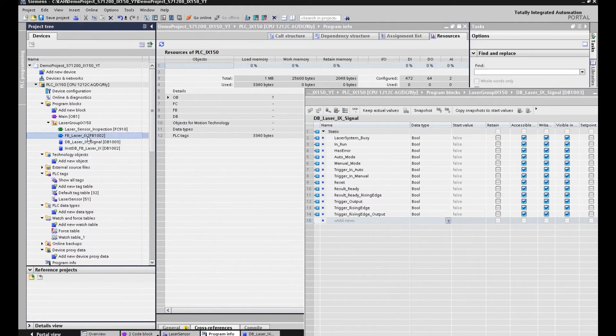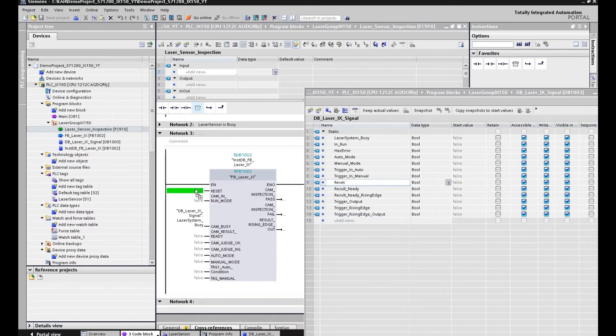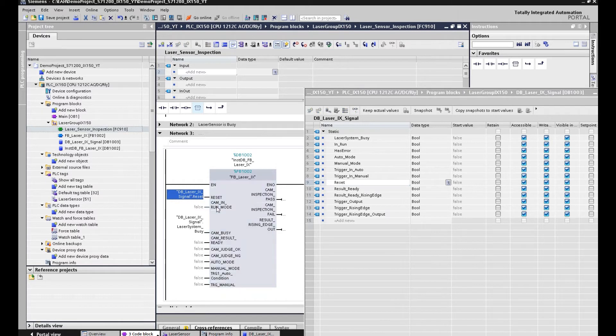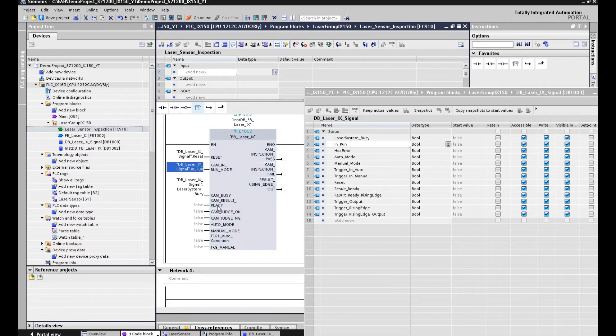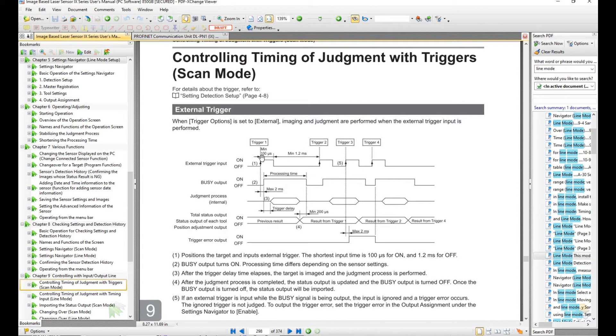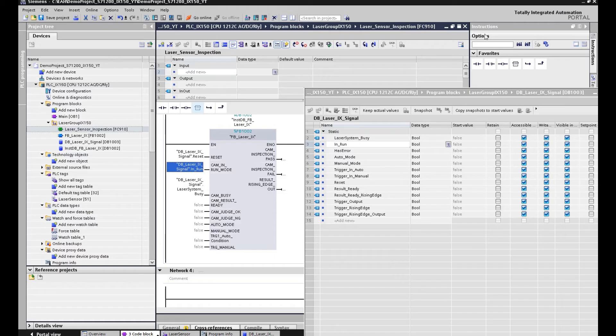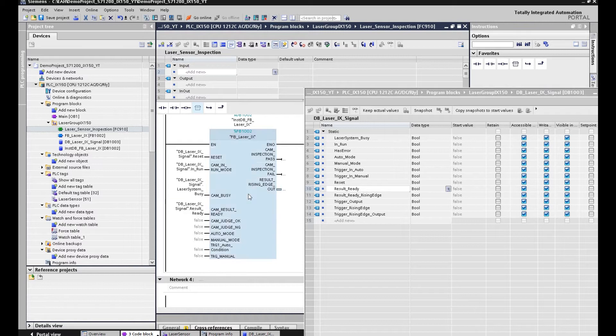We go back to our function. From here, we can connect the reset to this reset tag, and this reset tag can be controlled by our sequence. And the camera in run mode — we can define the camera in run mode, so we connect this in run mode. And for camera result ready, we go back to this timing chart from scan mode. From this chart, when the busy goes from 1 to 0, at that moment the result from the trigger is ready.